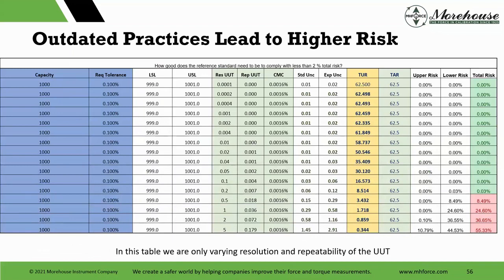This is a little more confusing. That's on the spreadsheet, but this spreadsheet has so many options, and it'll allow you to vary repeatability conditions and do everything else. So this table was created. We made some random generators and said, let's vary the repeatability and resolution only. And we kept our CMC, that's the dead weight that's used. And it said, how good does the reference standard need to be to comply with less than 2% risk?